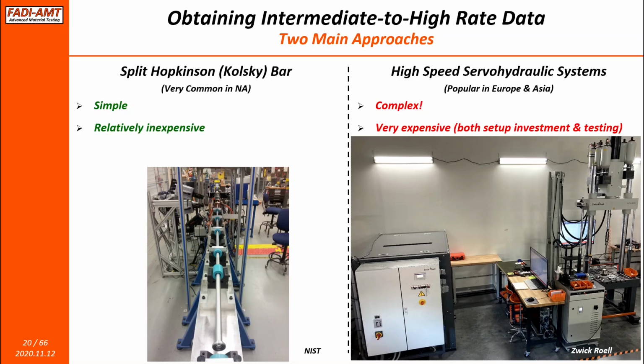On the right-hand side, when we go to the servo-hydraulic systems, or the high-speed servo-hydraulic systems, in principle, as I mentioned earlier, it's a tension machine that just goes faster. In reality, it's a little bit more complex than that, and therefore it is expensive.